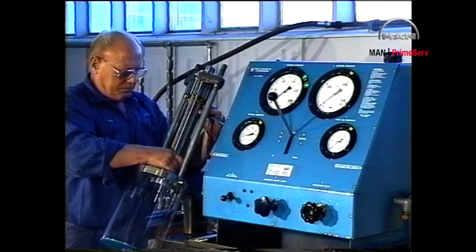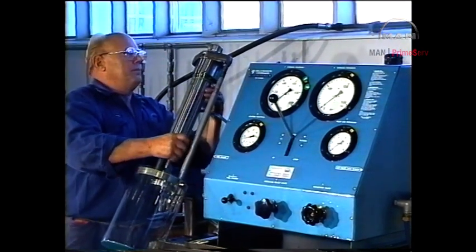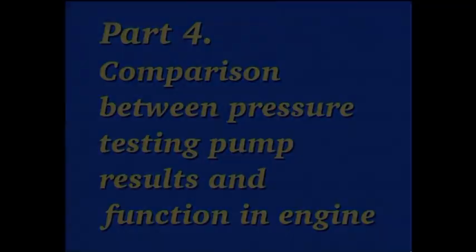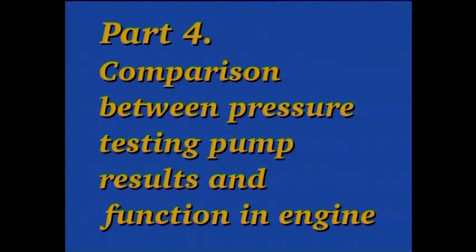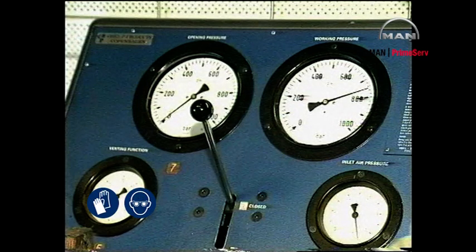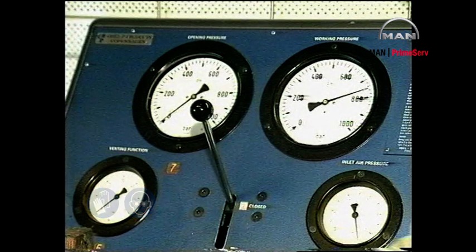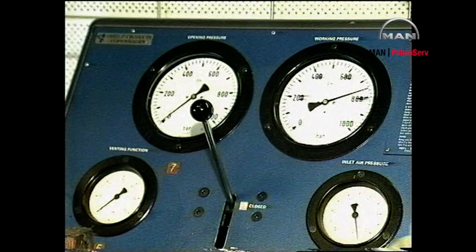After the fuel valve has passed all the tests, it can be mounted in the cylinder cover. The main objective of the normal tests shown in part three of this film is to ensure that the valves function at the correct opening pressures and that they seal tightly. As the injection capacity of the engine fuel pump is much greater than that of the pressure testing pump, atomization will be ensured during service provided that the fuel valve passes the normal tests.